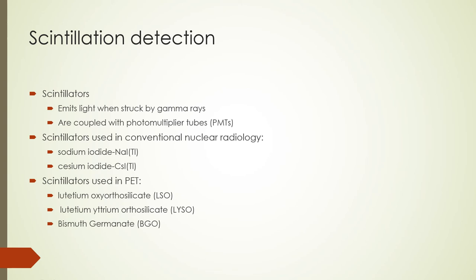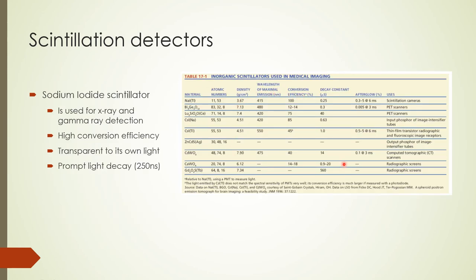Most scintillator-based detectors in nuclear medicine are operated in pulse mode and act as paralyzable systems. Algorithms may be incorporated to account for dead time losses. This table shows some properties that are desirable in scintillators. Sodium iodide is used in x-ray and gamma-ray scintillation cameras. It has 100% conversion efficiency with a fast decay constant of 250 nanoseconds and low afterglow. Other desirable properties for scintillators include high densities and high atomic numbers, which translates to high attenuation coefficients for gamma rays. Emission light should be matched to the spectrum of the detector.